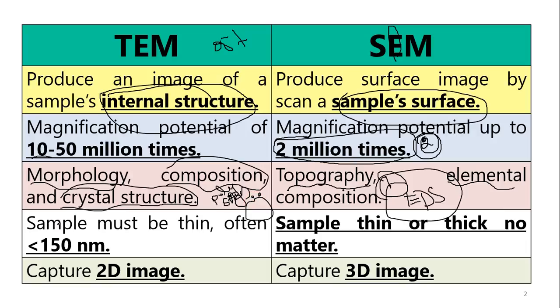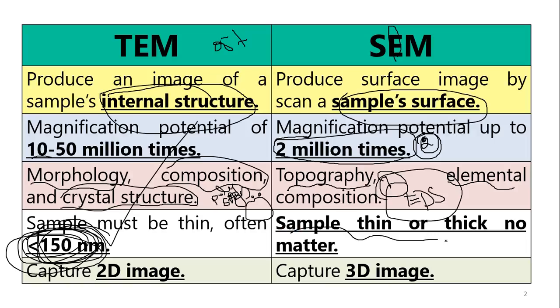For TEM analysis, the sample must be very, very thin because we want electrons to pass through — the sample should be below 150 nanometers. For SEM, the sample may be thin or thick; we do not have any problem as long as the sample fits within the sample holder.